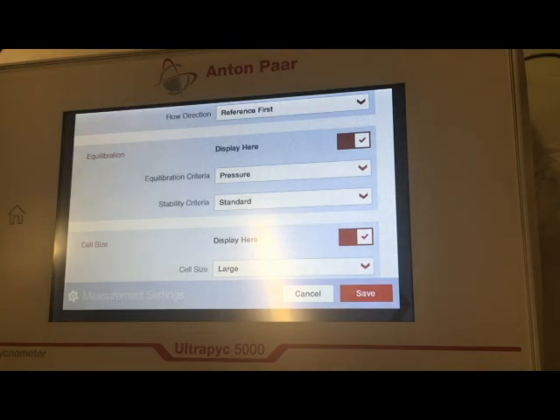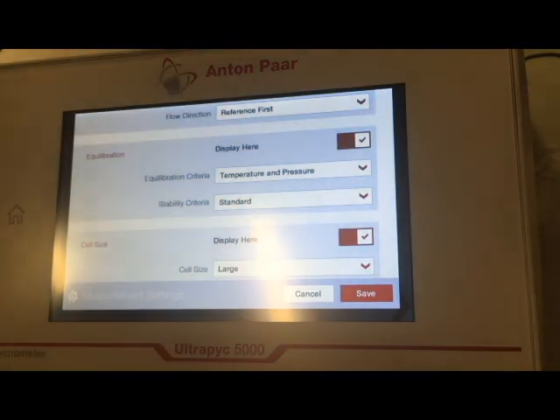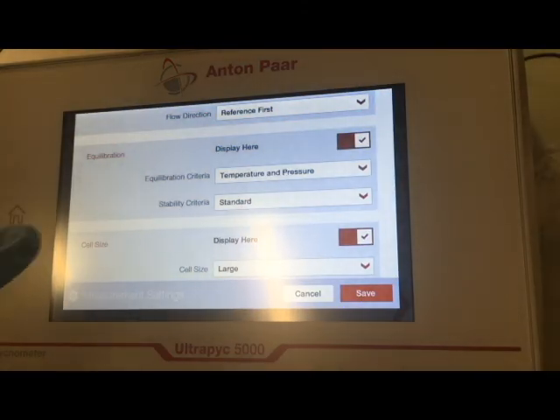The third equilibration criteria is temperature and pressure, meaning the machine is going to wait until the temperature and the pressure are both stable through all parts of the machine before moving on to the next cycle. This is the most precise of the 3 options for equilibration criteria and is going to give you the best results, but is also going to take the longest. Again, we have 3 options for stability criteria: standard, fast, and high precision. Choose those based on your application.